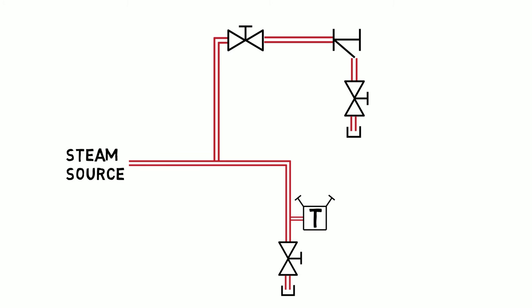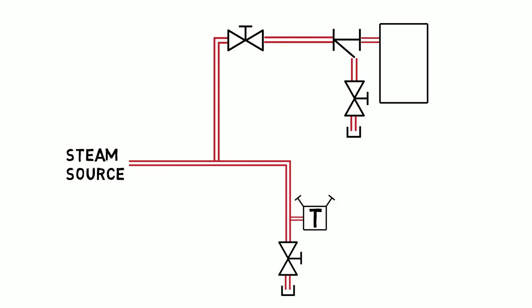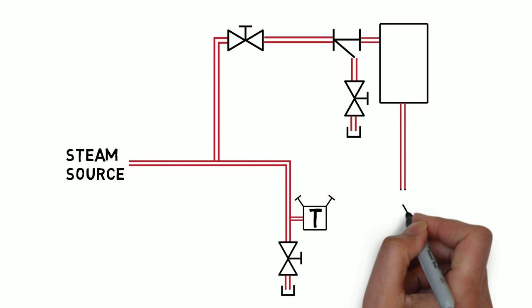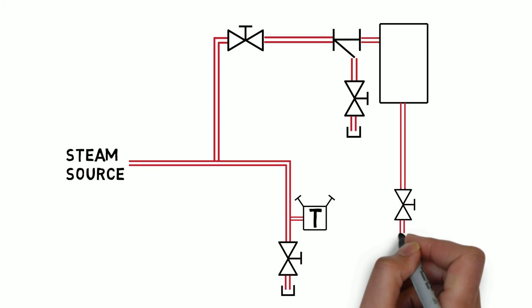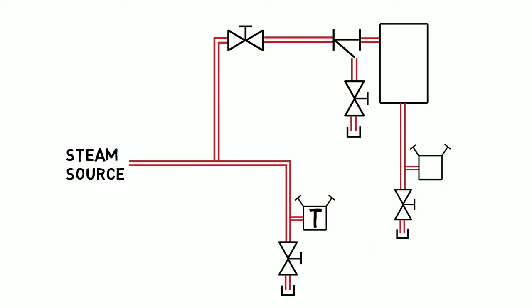The steam is then directed through a steam separator to ensure optimum clean and dry steam downstream free from water droplets and particles. From the bottom of the separator, another drip leg and steam trap drain away the removed condensate.